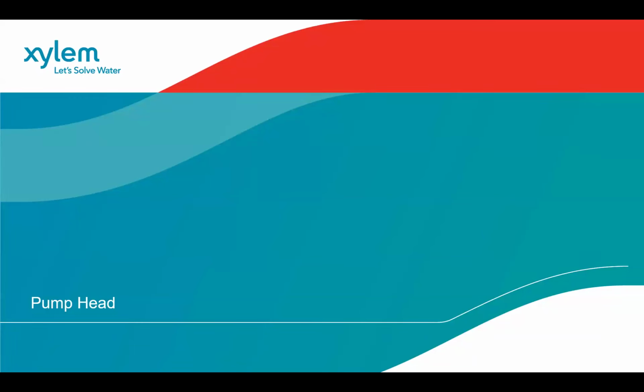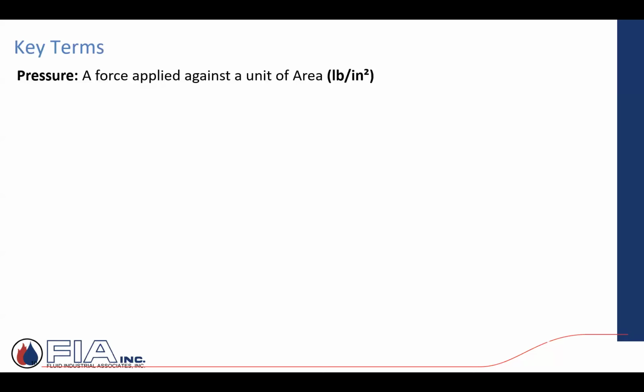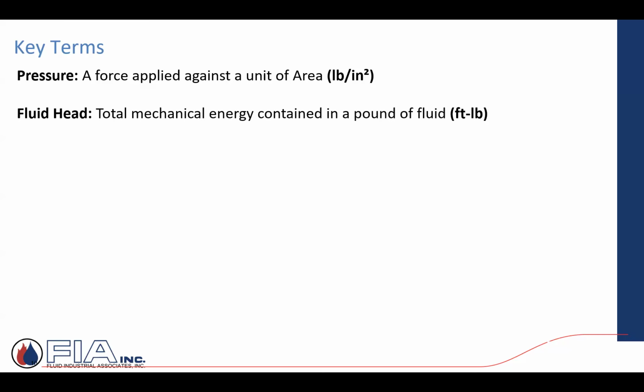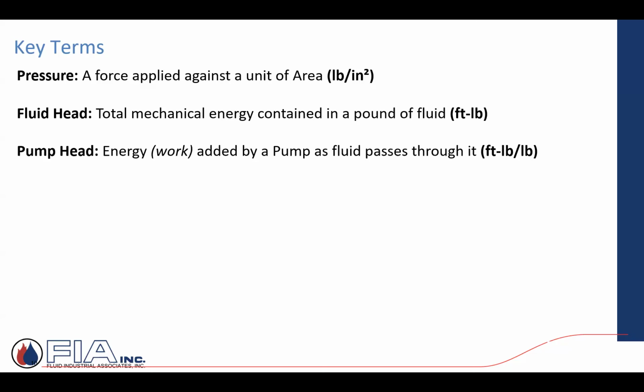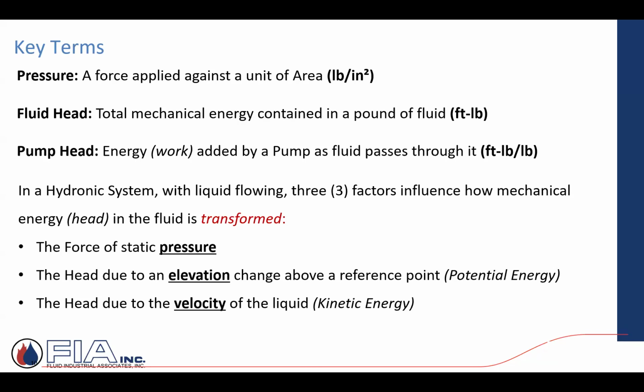So talking flow rate, the second part of that pump curve was pump head, or that foot pounds of energy. So what is pump head? There are just a couple of terms that you come across. Pressure: force applied against a unit of area. Fluid head: mechanical energy contained. Pump head: the energy or the work added by the pump as the fluid passes through the volute. So in a hydronic system, with the liquid flowing, three factors influence the mechanical energy head and how it's transformed. You've got the force of static pressure, a head due to elevation change in an open system, and then the head due to the velocity of the liquid, which would be what the pump has added through centrifugal force.